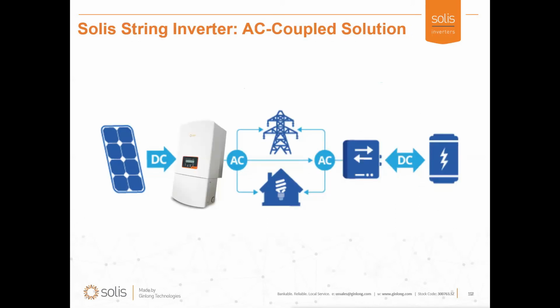AC coupled systems, such as Tesla and Sonnen, consist of a battery, auto transformer, and inverter. They are not directly connected to the PV string inverter, but are instead connected to the home. The PV system and the battery system essentially share the home and need only to recognize when the other is generating so that there isn't an accidental oversurge of power.